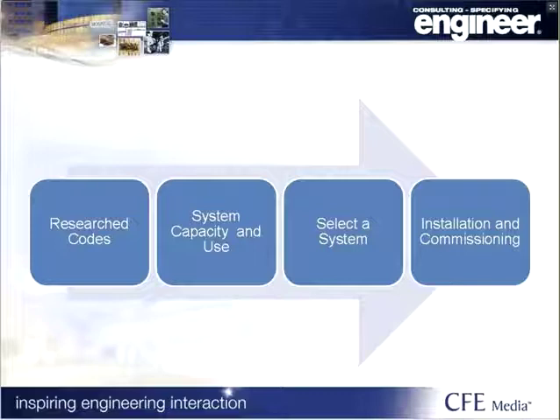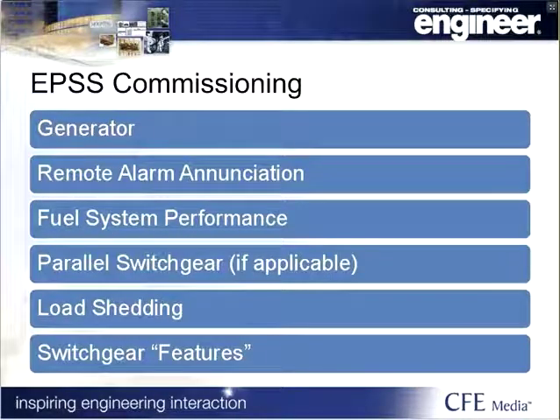Okay, so as professionals designing and selecting this equipment, our responsibilities don't end with just the specification. We need to make sure that it performs how we expect it to, and that comes down to commissioning. So you have to look at the EPS as a system. There's a lot of different components, and there's a piece that all works together and ties together. So these are a couple of different things that we're going to run through as part of the commissioning effort. Identify a couple of key points that you're going to need to look at if you do get an opportunity to commission an EPS system.